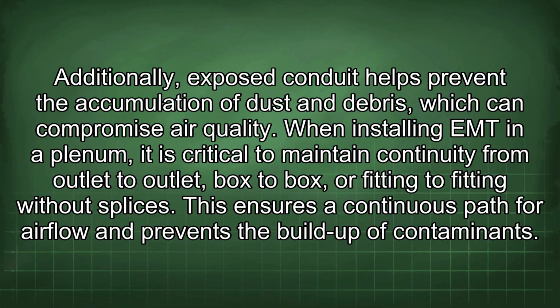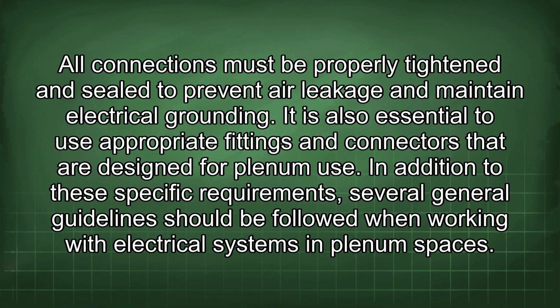When installing EMT in a plenum, it is critical to maintain continuity from outlet to outlet, box to box, or fitting to fitting without splices. This ensures a continuous path for airflow and prevents the buildup of contaminants. All connections must be properly tightened and sealed to prevent air leakage and maintain electrical grounding. It is also essential to use appropriate fittings and connectors that are designed for plenum use.